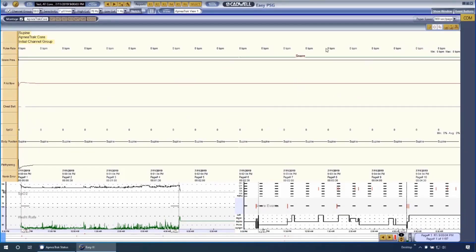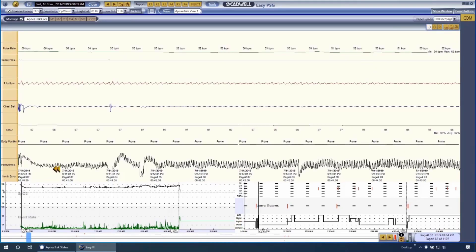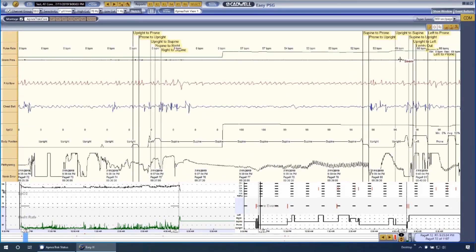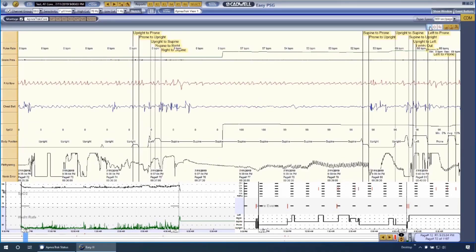You will be able to place markers for lights out and lights on to account for the time the patient wore the device and you will be able to see all instances in which the patient pressed the event button. You will also be able to score new events and edit events already in the record.